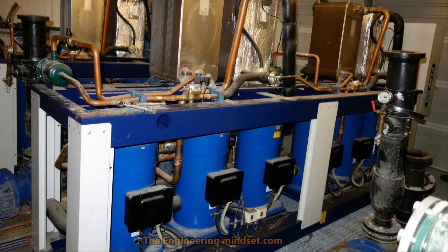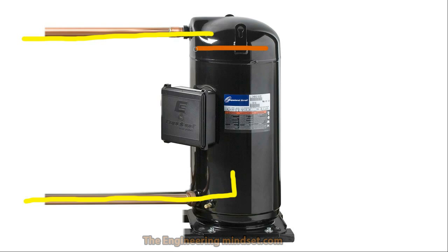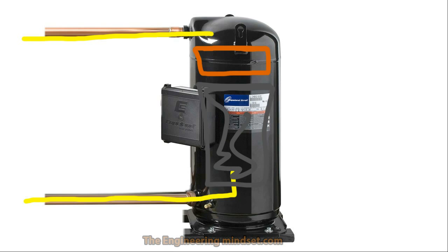The next one we'll look at is the scroll-type compressor. Here's an example of a scroll-type compressor chiller — they're pretty common on air-cooled chillers, though this is a water-type one. You'll usually find that one compressor isn't enough, so they'll have banks of them. These compressors usually have their inlet at the bottom, which passes through, with the outlet exit there. The compression takes place at the very top in a fairly small chamber, with most of the unit being the motor and stator. The refrigerant comes in through the inlet, makes its way through the motor, and passes into the scroll.